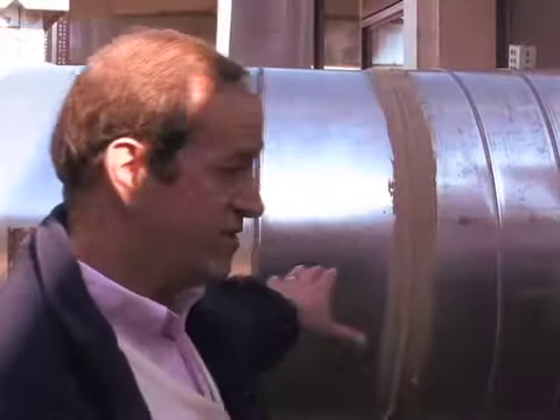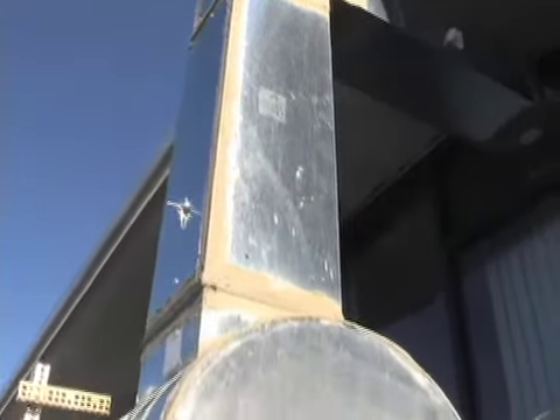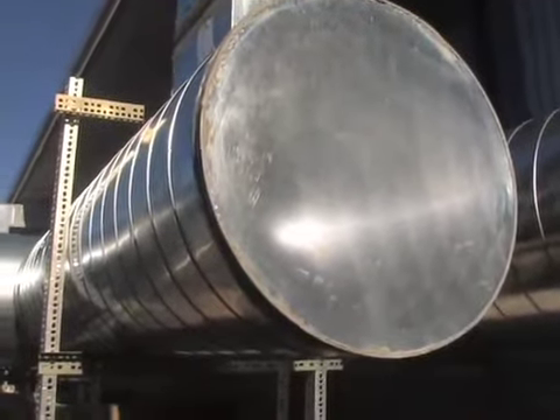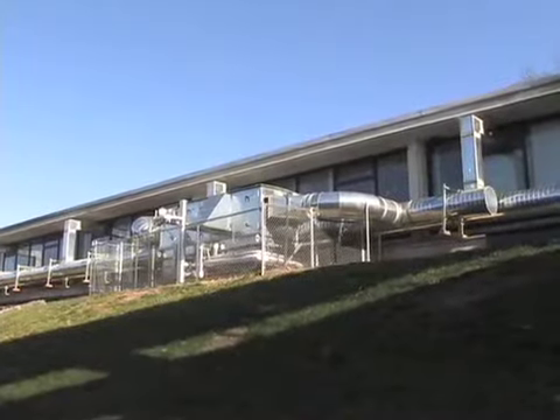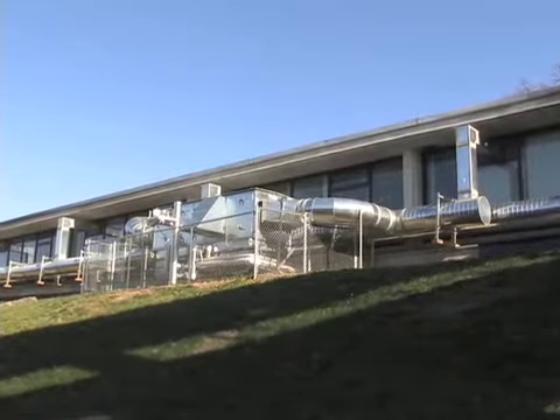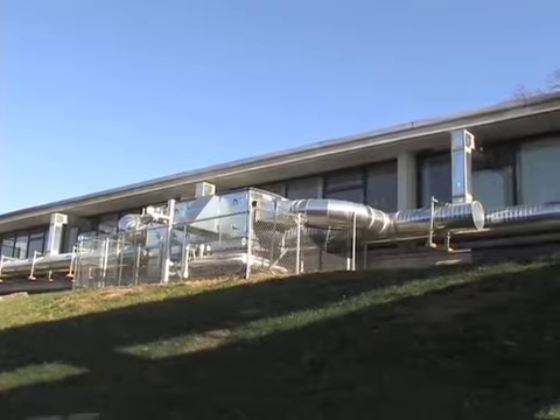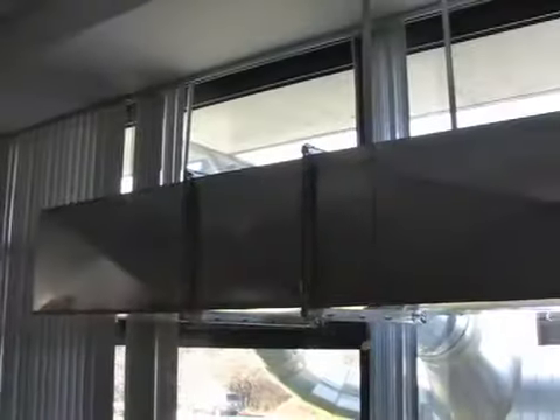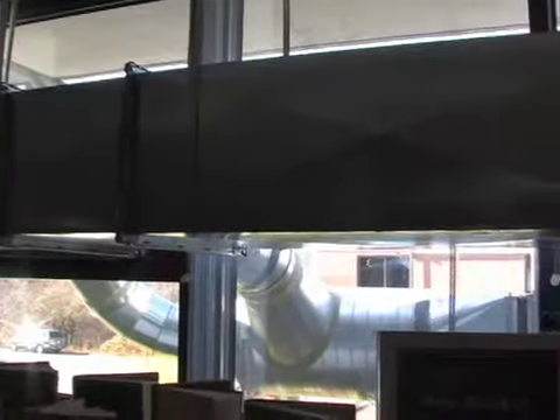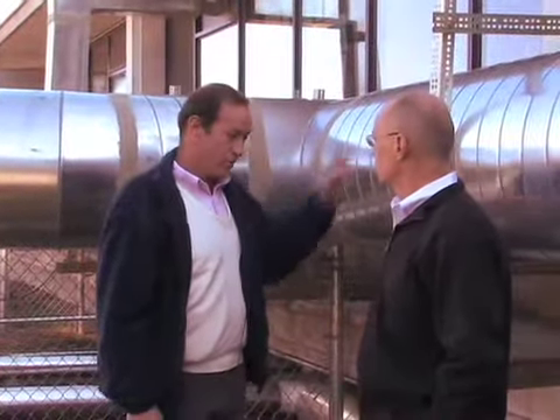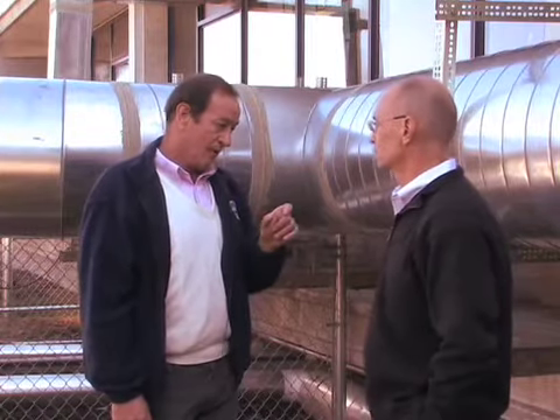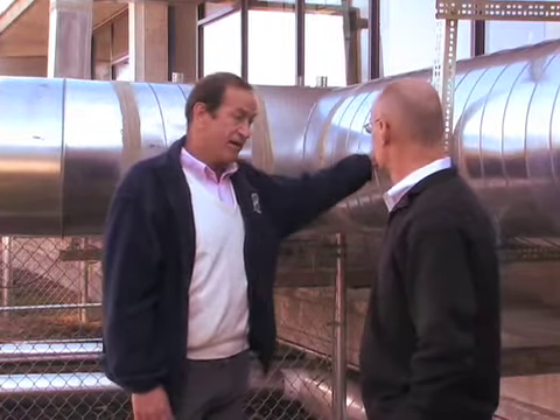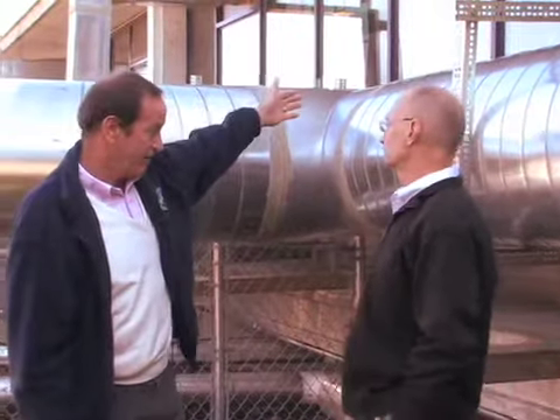Let's just take a look at the piping you see here. This 24-inch diameter pipe is actually double walled with only 1 inch of insulation in between the two walls. With that being said, in order for this unit to become effective, as this unit is heated up with the steam coil on the inside and the air is passed over it, the air travels through these pipes and into the adjoining classrooms. But the first thing we have to heat are the pipes before we can actually heat the classrooms because of that 1 inch of insulation. And that's this ductwork here? That's correct. This is a double wall pipe with 1 inch of insulation in between. Only being 1 inch, it's a very low R factor. So we actually have to heat these pipes up before we can actually start heating up the spaces.